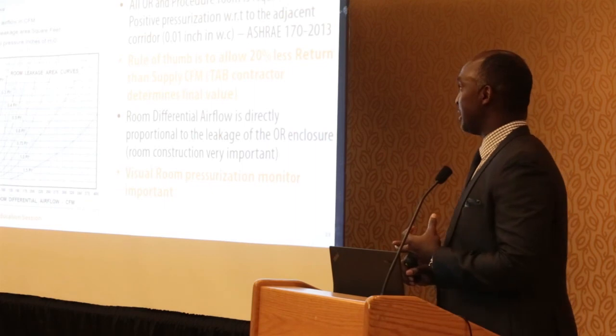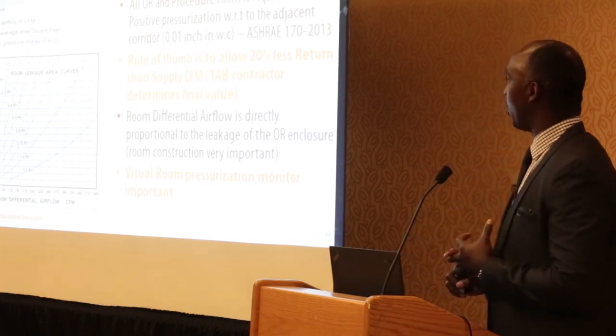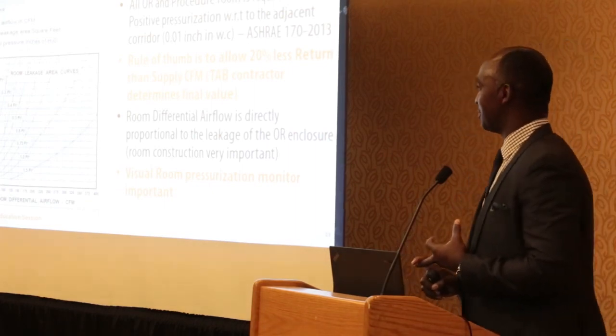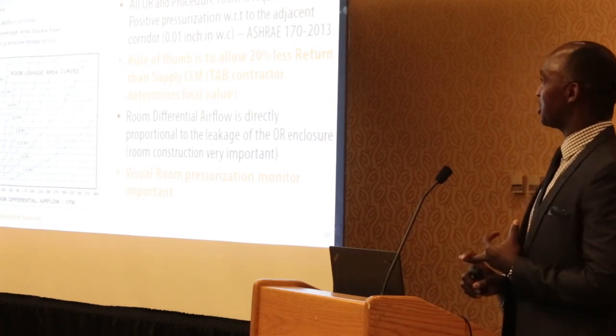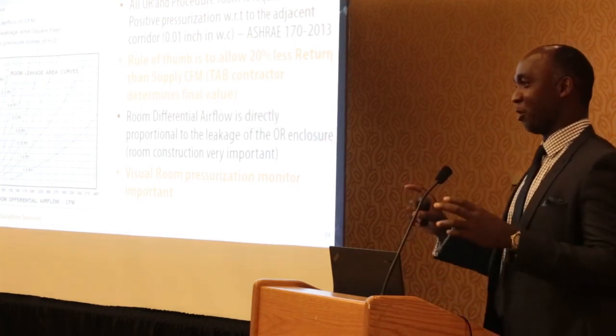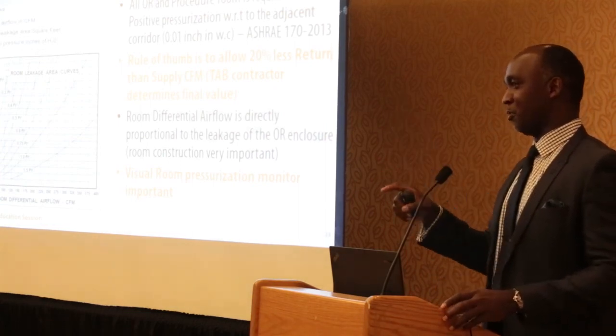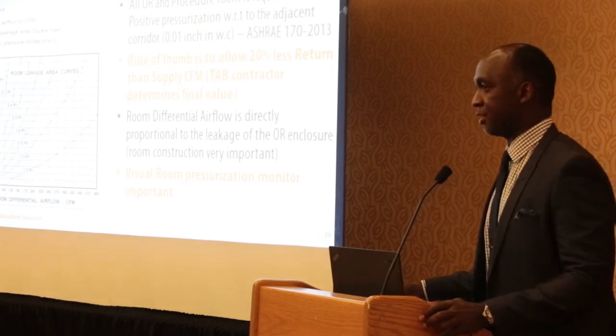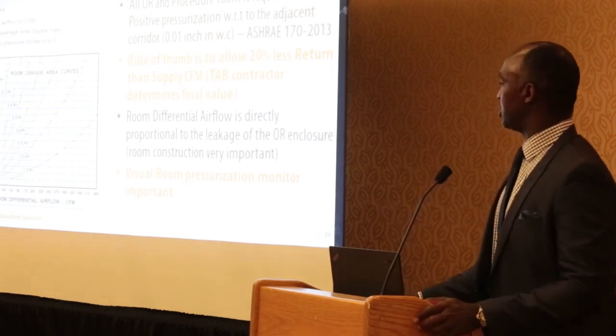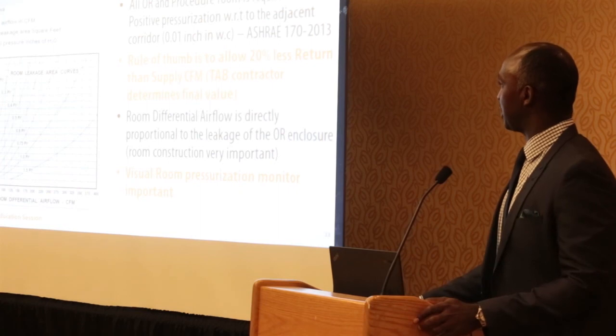But the ideal pressure requirement is 0.01 inch WC. And when you go into an OR room, if you have a visual monitor, you will see that it's going to be about that, or 0.002 or 0.015. That's where it's going to be.